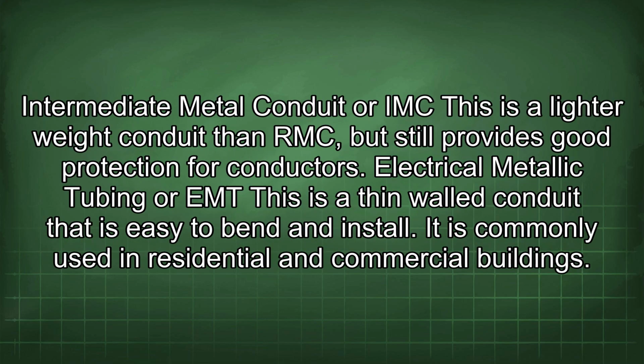Intermediate metal conduit, or IMC. This is a lighter weight conduit than RMC, but still provides good protection for conductors. Electrical metallic tubing, or EMT. This is a thin-walled conduit that is easy to bend and install. It is commonly used in residential and commercial buildings.